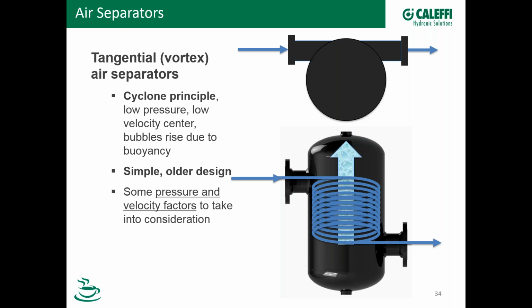On this type of separator, velocity is important, as you mentioned, because you're basically relying on the velocity to send the air bubbles towards the middle and then up out the vent. A problem with these is sizing them based on pipe size. If your pipe has been sized to deliver 4 feet per second, and you sized your separator to match that pipe size, there might be insufficient velocity going around that vortex to create the action needed to get rid of the air bubbles.